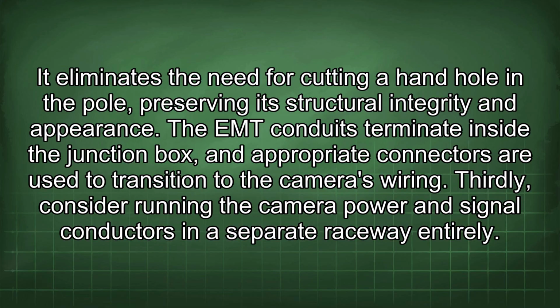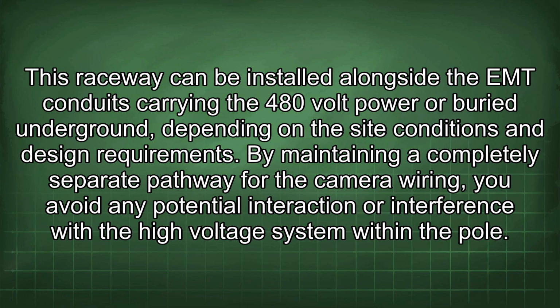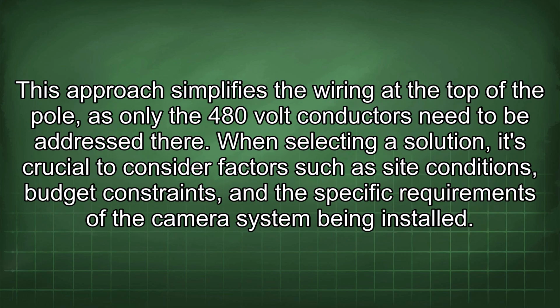Thirdly, consider running the camera power and signal conductors in a separate raceway entirely. This raceway can be installed alongside the EMT conduits carrying the 480-volt power or buried underground, depending on the site conditions and design requirements. By maintaining a completely separate pathway for the camera wiring, you avoid any potential interaction or interference with the high-voltage system within the pole. This approach simplifies the wiring at the top of the pole, as only the 480-volt conductors need to be addressed there. When selecting a solution, it's crucial to consider factors such as site conditions, budget constraints, and the specific requirements of the camera system being installed.